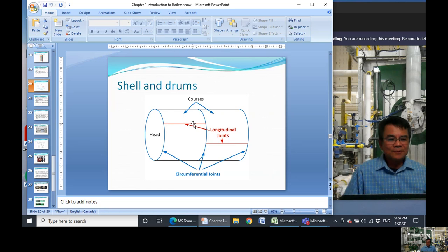So lots of times, you know, just bending a piece of metal, cold working a piece of metal, and the seam in here finally gave, and then the whole thing just blew apart. Okay, and the exact cause, nobody knows. Lots of people blame the welding in here is no good. And somebody blamed the water treatment is no good. There's a hot spot, and then the heat will damage the metal. Something like that. Okay.